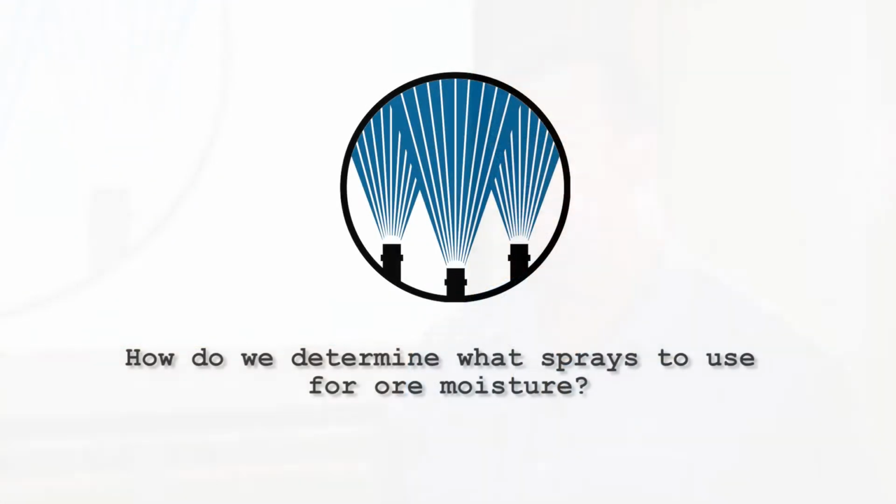Generally on the screen house they use dust extraction systems. Because they're using dust extraction systems, you can't add water because it blocks the screens as well. So the option they usually have is to put a fogging spray around the bottom side of the conveyor to suppress the dust from expanding outwards, so it gets pushed down to ground level and can be washed away.